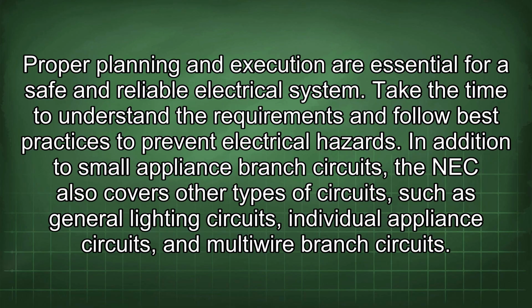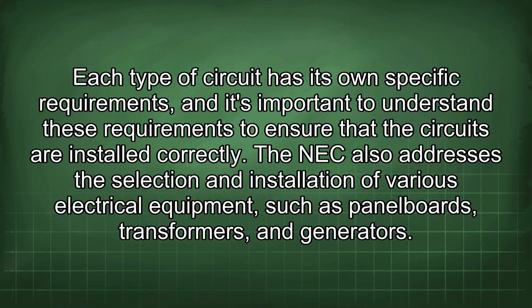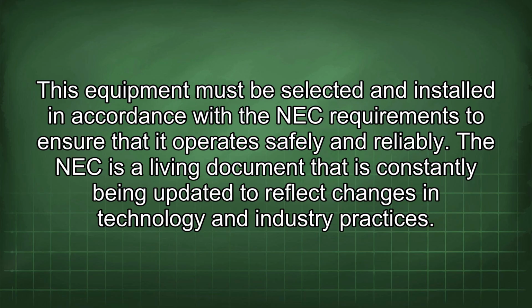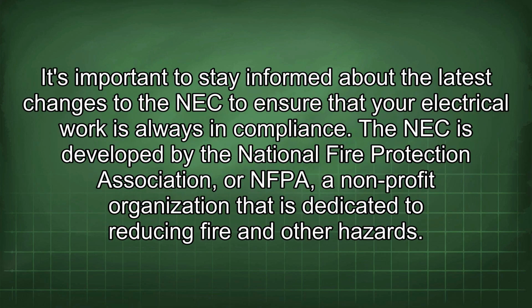In addition to small appliance branch circuits, the NEC also covers other types of circuits, such as general lighting circuits, individual appliance circuits, and multi-wire branch circuits. Each type of circuit has its own specific requirements, and it's important to understand these requirements to ensure that the circuits are installed correctly. The NEC also addresses the selection and installation of various electrical equipment, such as panel boards, transformers, and generators. This equipment must be selected and installed in accordance with the NEC requirements to ensure that it operates safely and reliably. The NEC is a living document that is constantly being updated to reflect changes in technology and industry practices. It's important to stay informed about the latest changes to the NEC to ensure that your electrical work is always in compliance.